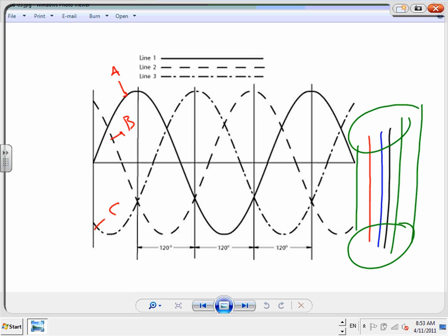The circuit has a major concept, guys, called impedance. Just remember one thing: the impedance of the circuit is minimized as you group the conductors together, and also there is no inductive heat. Remember the term inductive heat when we group them together. So when we group them like this, we minimize impedance, number one, and also eliminate induction heat.